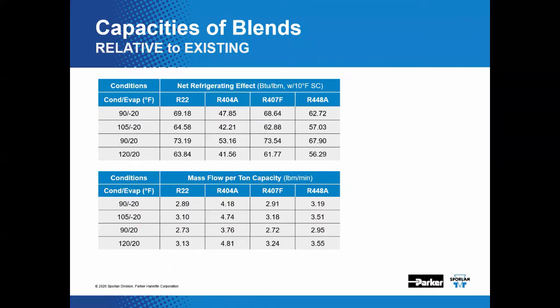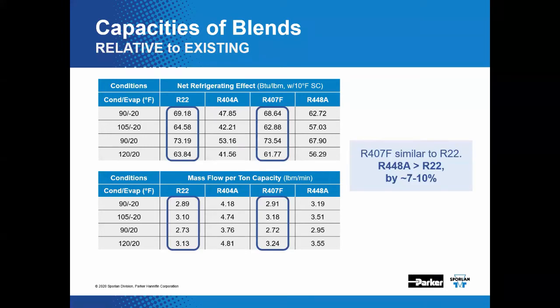When we start to consider valves and controls for these refrigerants, particularly in the case of system retrofits, one of the first things we need to consider is the capacity of the refrigerant relative to the ones we are replacing. The top chart here shows net refrigerating effect, or NRE, for R22, R404A, R407F, and R448A at a few different low temp and medium temp conditions. The lower chart is the resultant mass flow of each that we need per ton of capacity. There are a lot of numbers up here, so let's look at some trends and similarities. We find that R22 and R407F are very similar in terms of NRE and mass flow.